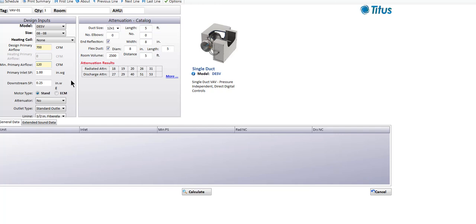Downstream static pressure is the static pressure drop between this unit and the room it's serving — that's the pressure drop created by the discharge ductwork, the diffuser takeoffs, balancing dampers, flex duct, and the diffusers or grills on the end of the duct. The program defaults to a quarter inch of downstream static pressure, which is the preferred number most engineers like to use. By selecting a quarter inch, it makes sure we're covered — we need enough inlet static pressure to overcome the pressure drop of the box, any associated coils, and that downstream static pressure.